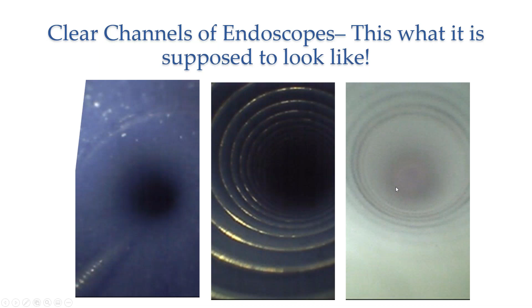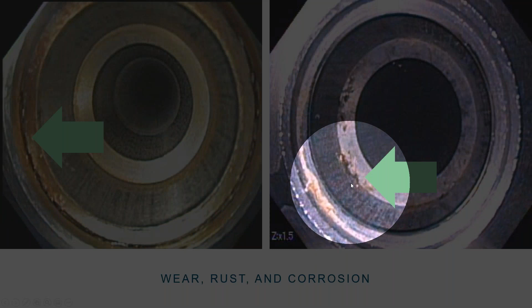The second one is the scope channel. Sometimes when you get a scope, do you know what a good scope is? If you have a brand new endoscope and you look inside it, you see that it's a pretty clean area. This is the articulation area that moves. This is the inside of the scope, and for the most part it is pretty clean. But then you can go over time and look at it. For example, these channels have gouges in them. Then you can look over time to see if there's an issue, knowing that if you have a gouge, you could damage the inside of the scope, it could start leaking inside and compromise the patient. Or, in this case, you require some magnification to see some of these issues: you see the rust, the damage, and corrosion inside the scope.